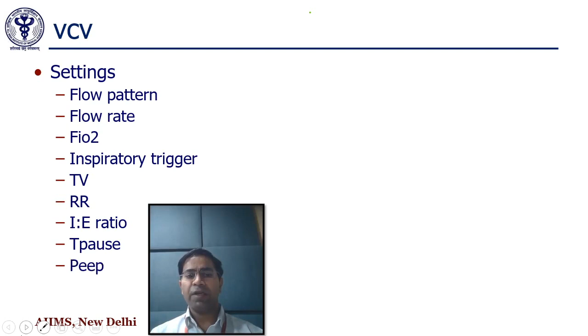If you talk about the PEEP, then we can choose the PEEP depending upon the compliance of the lung. If the compliance is poor, then we can go for high PEEP, more than 10. If the compliance is good, then we must stick to less than 10 PEEP. We can choose PEEP according to the ARDS network table, or on the basis of the lower inflection point of the pressure volume curve, or we can derive it by using the compliance optimization technique. In this technique, we set a particular PEEP, see the compliance, then again increase it to know about the best compliance, and we keep the PEEP where there is the best compliance.